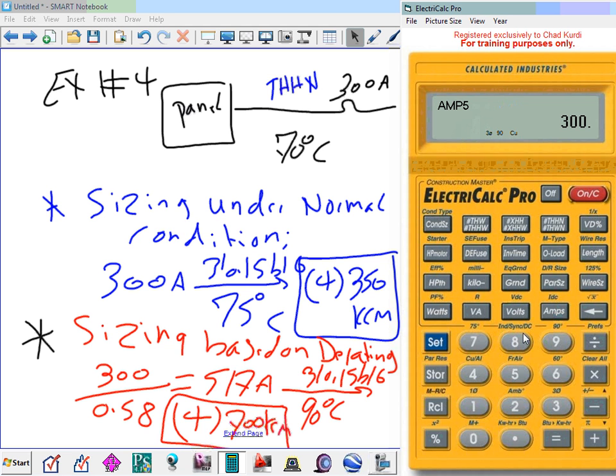The second thing I need to change is ambient temperature. What's my ambient temperature? 70. So you're going to hit set and 2. Why 2? If you guys look above 2, it says ambient. So I told the calculator, oh, by the way, we're boiling here. We're sitting at 70 degrees Celsius. And when you're done, you're going to hit wire size. And what do you get? 700 kcmil.